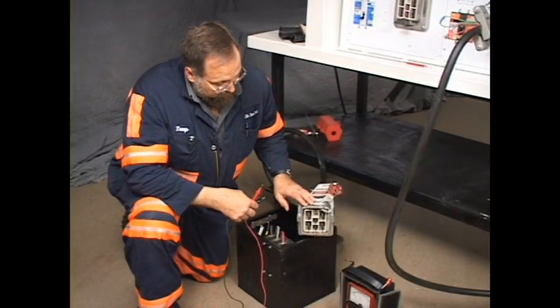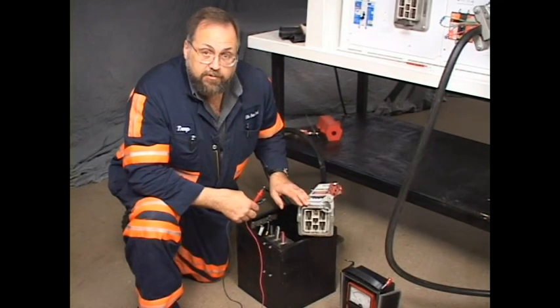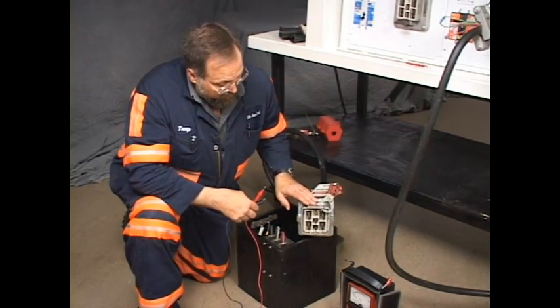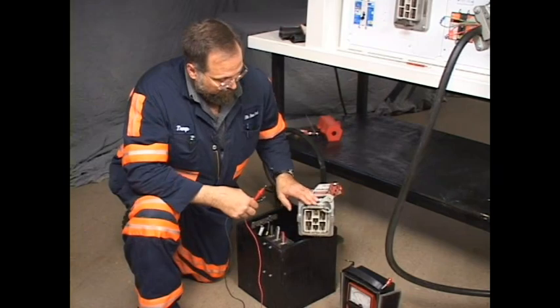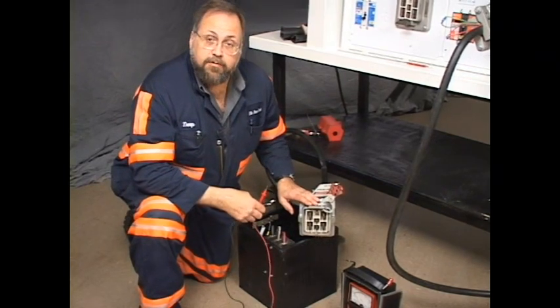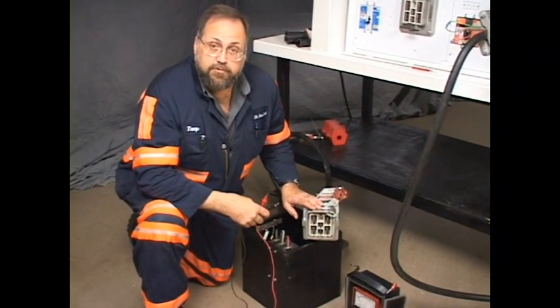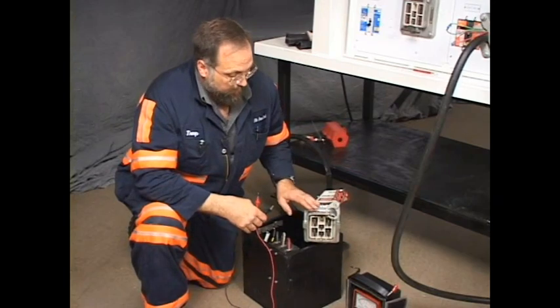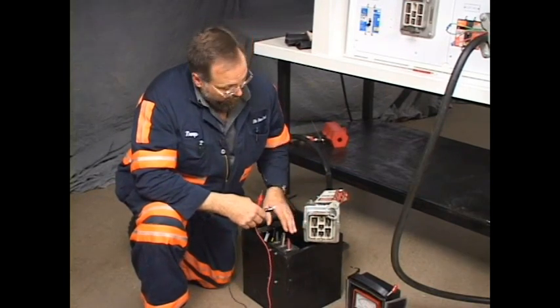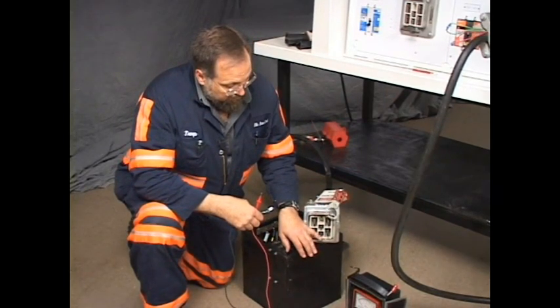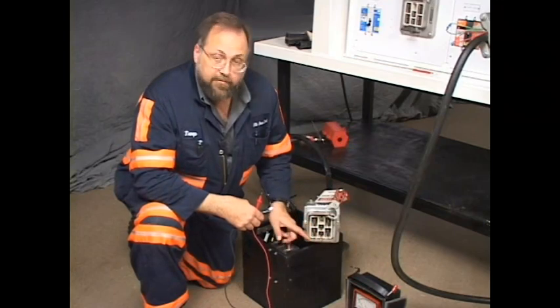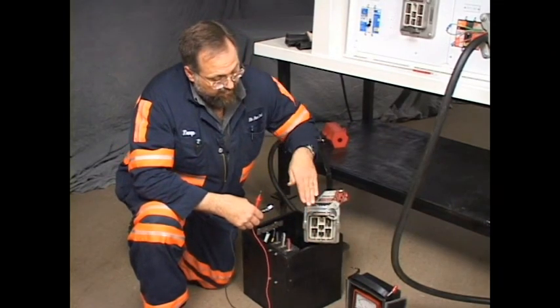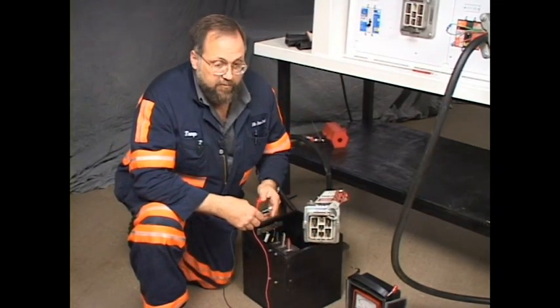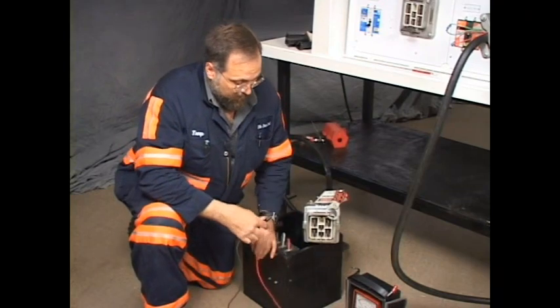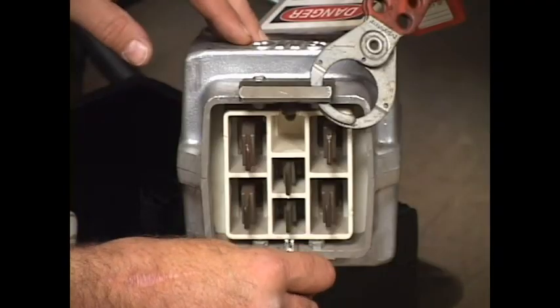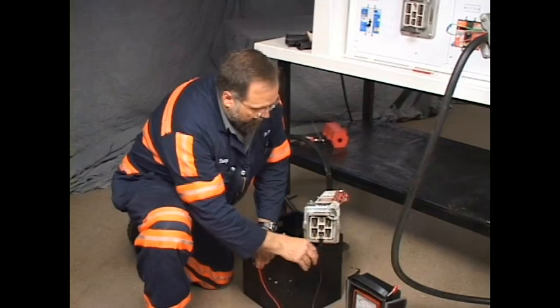Now, some people have trouble telling which one is which. If you remember from your studies in the book, the ground continuity monitor conductor is broken first when the cable is uncoupled or the cable coupler is removed. As you can see, this one in the center here is much shorter than the other two. As the cat head is hinged up and levered up, it would be the first one to break. So we know that's the pilot or monitor blade.